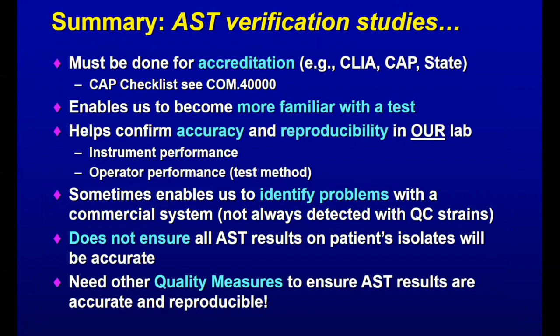It must be done for accreditation purposes, for CLIA, for your CAP, and in many states they have requirements as well. We did highlight here where you can find the verification requirements in the CAP checklist, and that's in the common checklist.